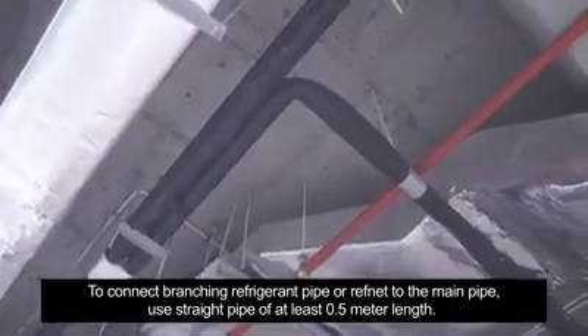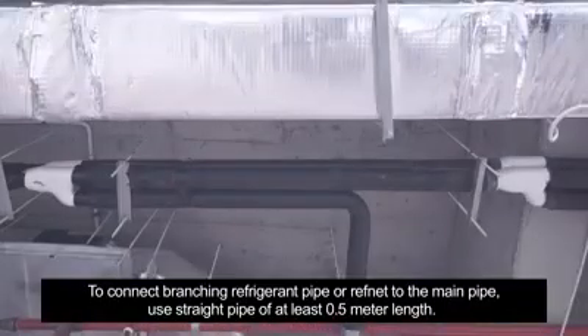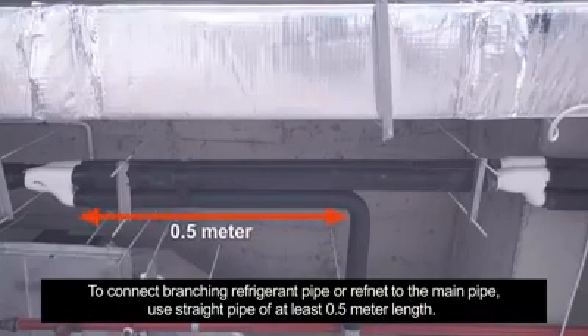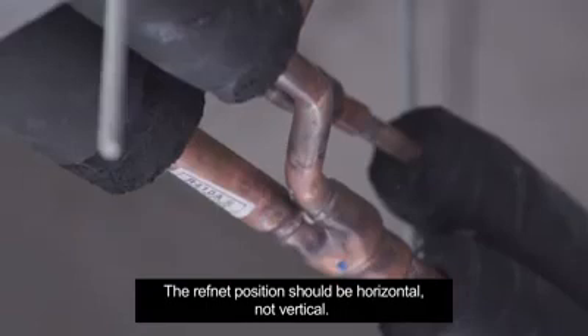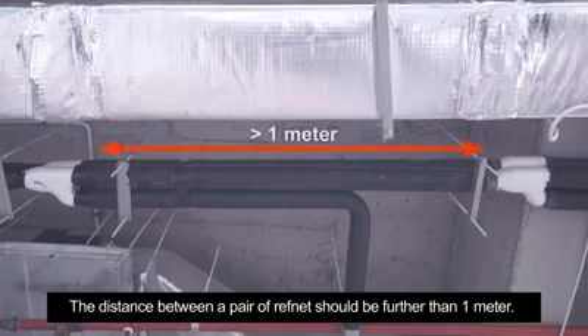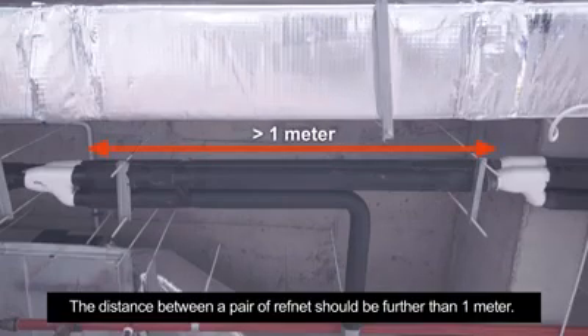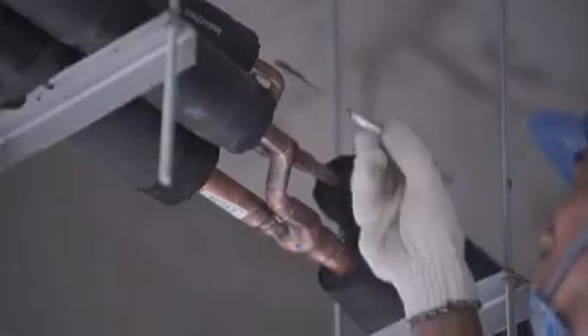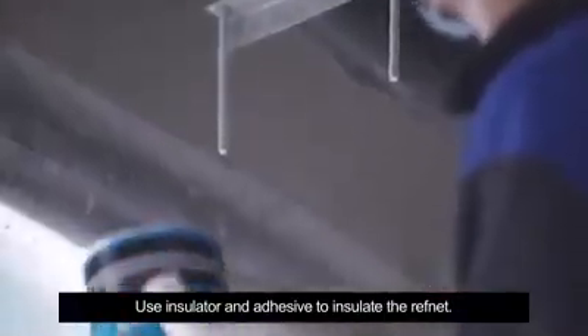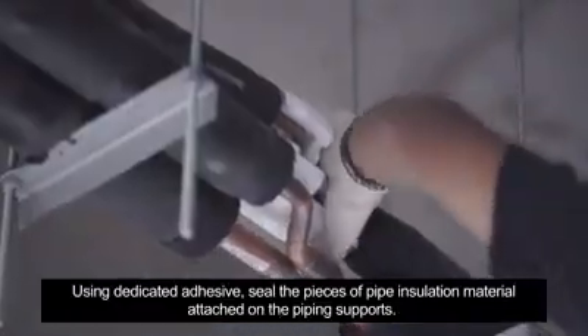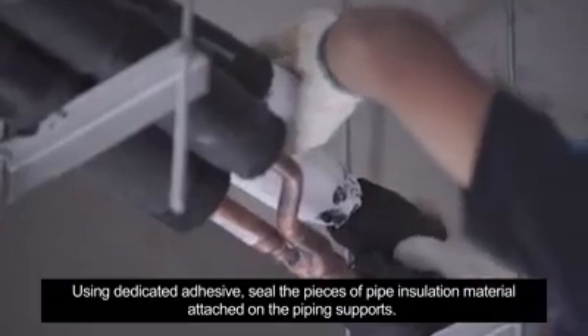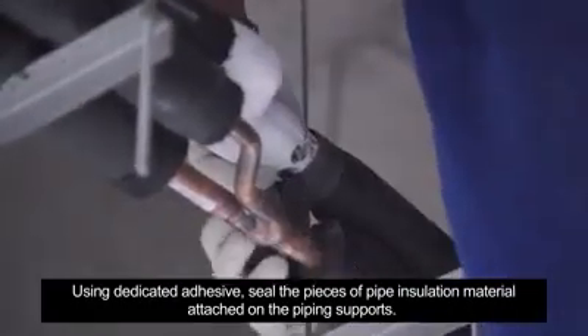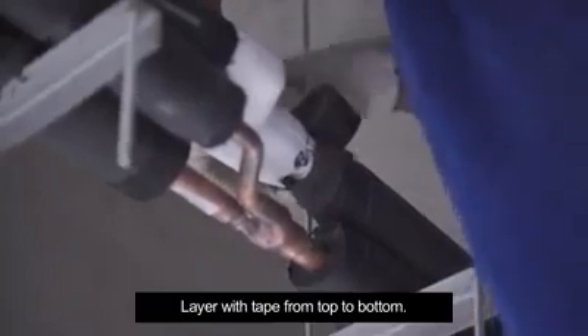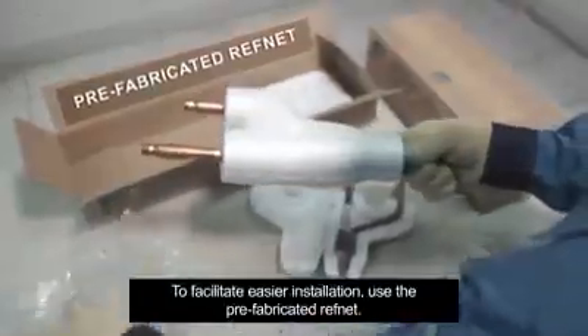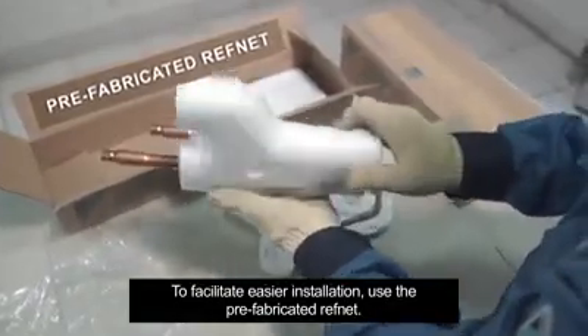To connect branching refrigerant pipe or refnet to the main pipe, use straight pipe of at least 0.5 meter length. The refnet position should be horizontal, not vertical. The distance between a pair of refnet should be further than 1 meter. Use insulator and adhesive to insulate the refnet. Using dedicated adhesive, seal the pieces of pipe insulation material attached on the piping supports. Layer with tape from top to bottom. To facilitate easier installation, use the prefabricated refnet.